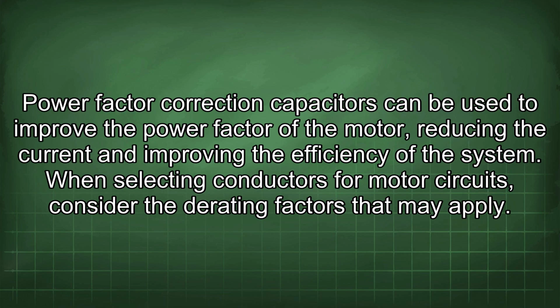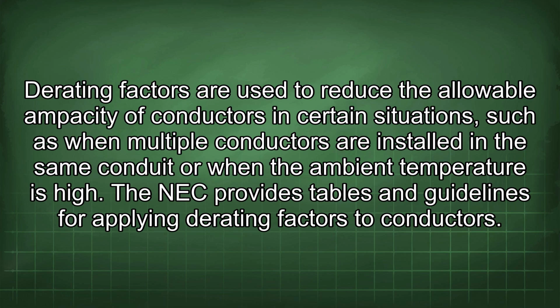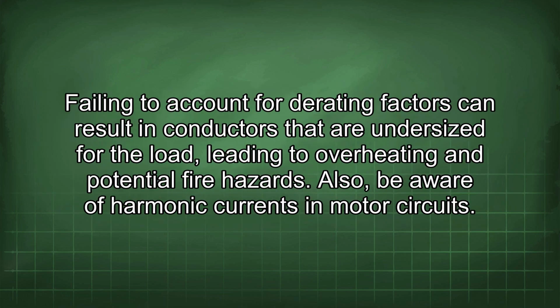When selecting conductors for motor circuits, consider the derating factors that may apply. Derating factors are used to reduce the allowable ampacity of conductors in certain situations, such as when multiple conductors are installed in the same conduit or when the ambient temperature is high. The NEC provides tables and guidelines for applying derating factors to conductors. Failing to account for derating factors can result in conductors that are undersized for the load, leading to overheating and potential fire hazards.